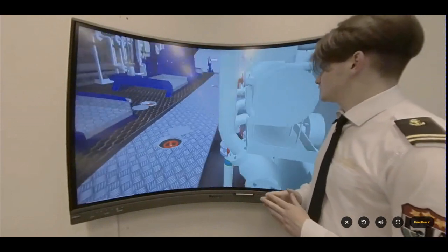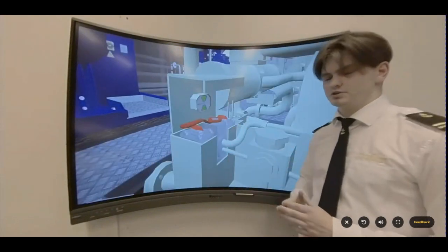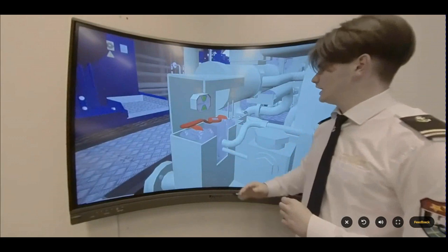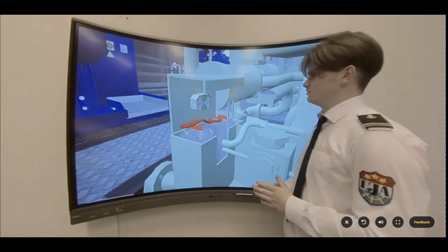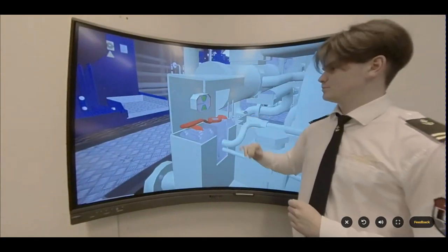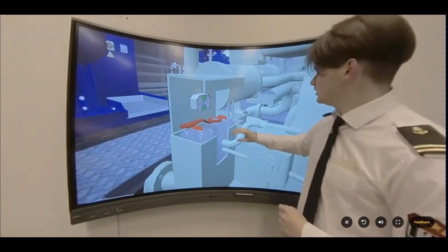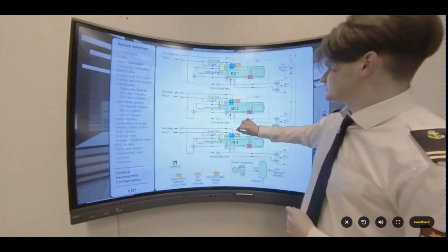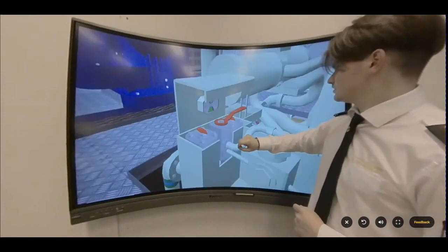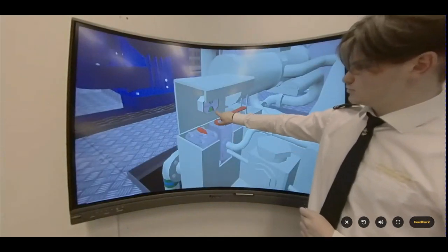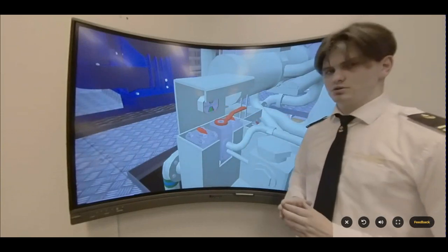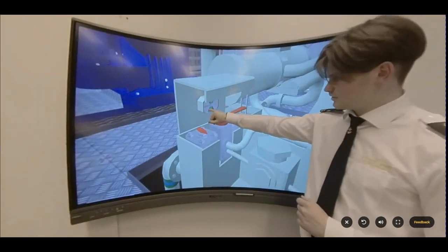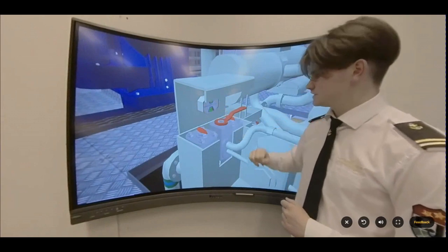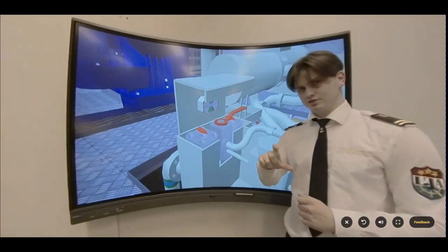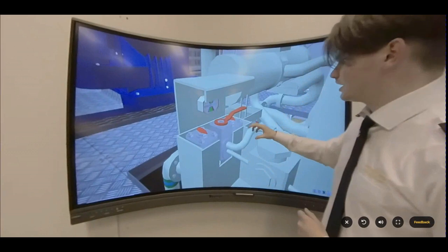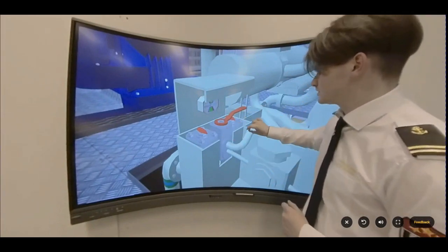Near the engine we also have filters for our fuel, and we can monitor the condition of the filters by checking the differential pressure. The number 1 generator is running now, so we can check the filters on number 1. Here you can see more red color showing on this equipment, meaning the difference in pressures is growing, and in one moment we'll have to switch filters.